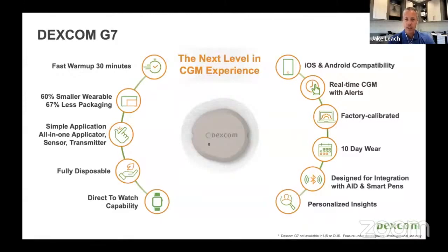The G7 is factory calibrated, designed to meet the rigorous iCGM standard that the FDA set forth when G6 was approved. It's a very high bar, and performance has to be shown across a very large glucose range in a lot of patients across different wear sites, whether it's the arm or abdomen. With G7, we have studied it and plan to launch it in a format where it can be used on the arm or on the abdomen per labeling. So that was an exciting advancement with G7.